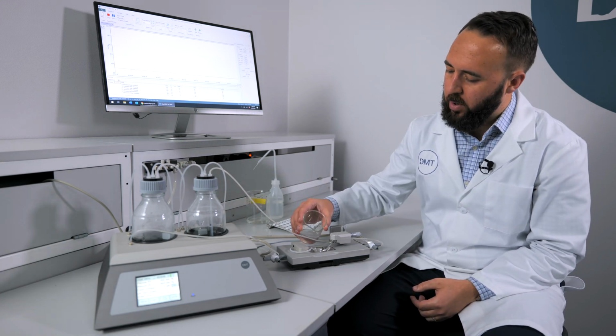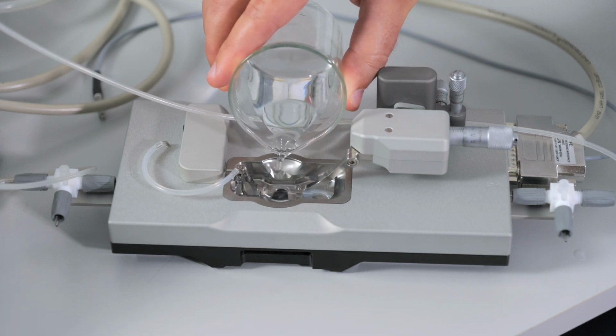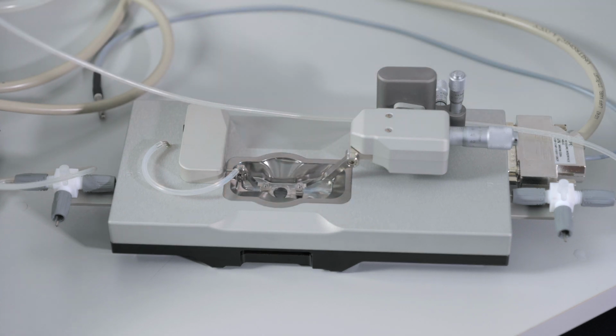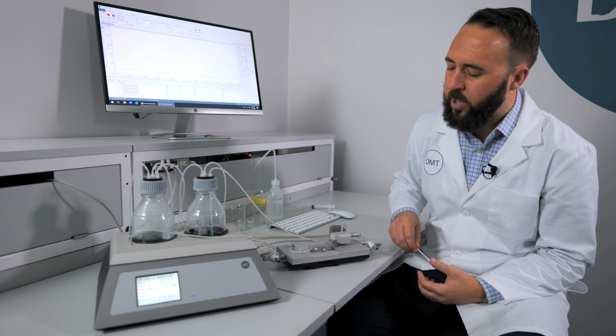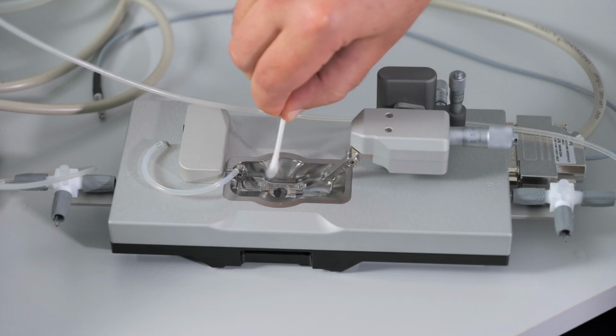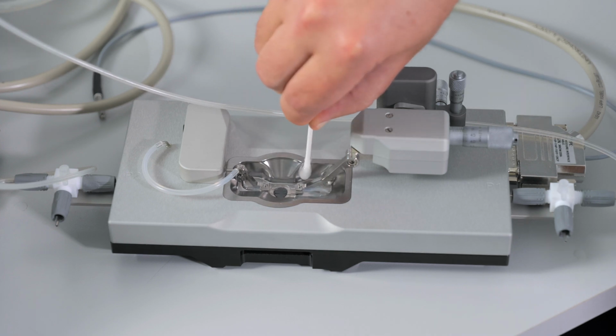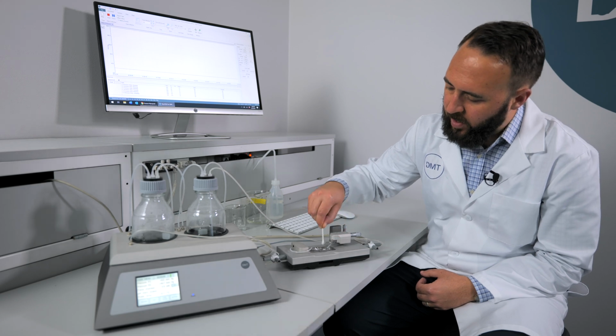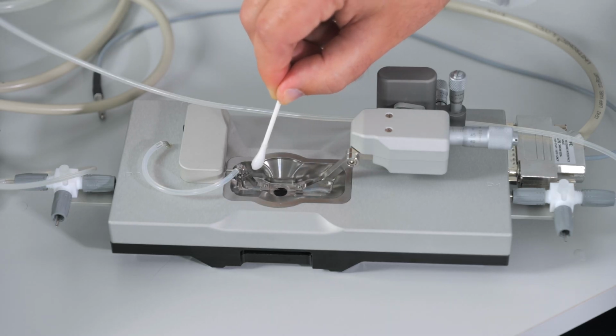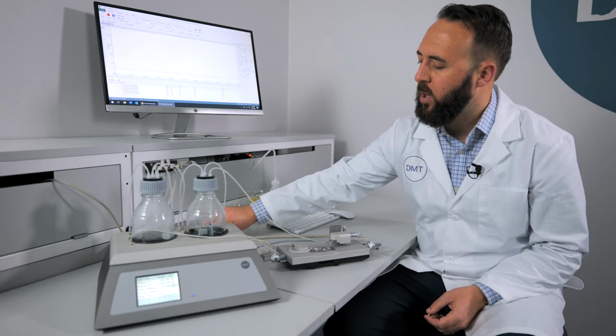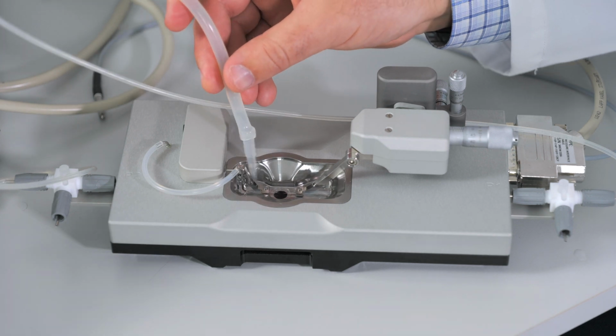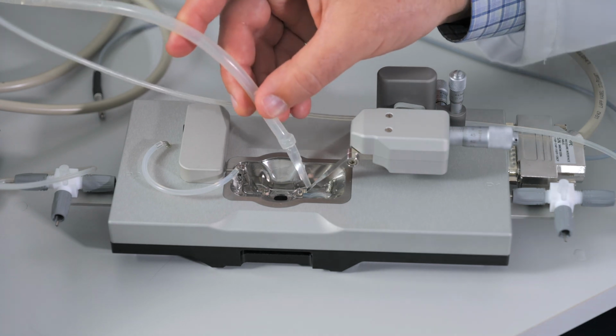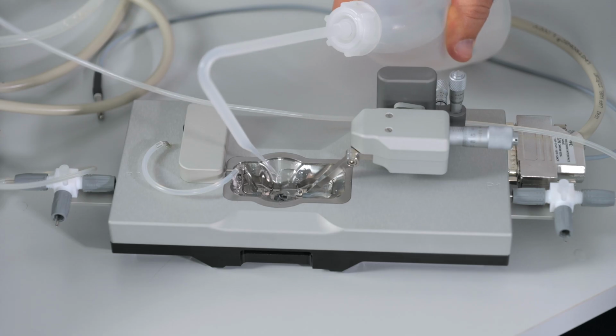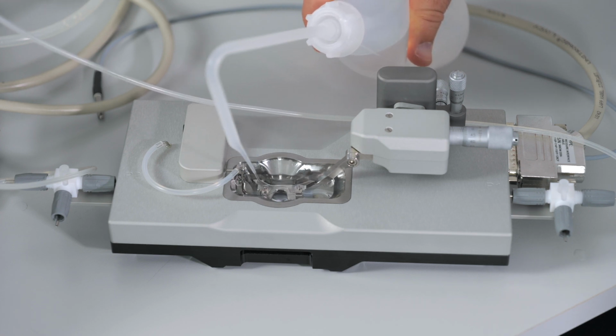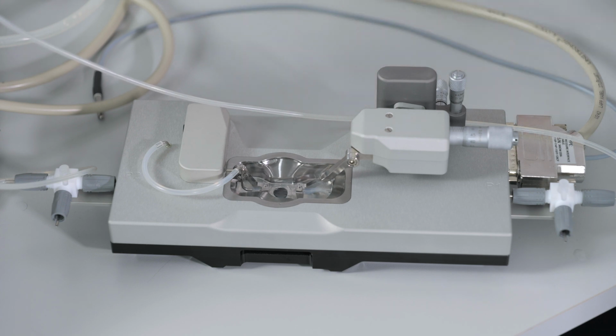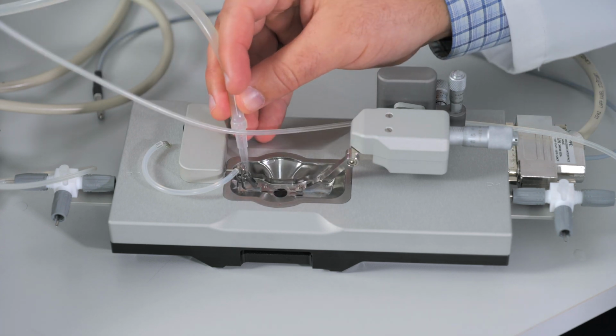You will fill the chamber with acetic acid and let it sit for 2 to 3 minutes. While it is sitting there, you can use a cotton swab to rub down the edges of the chamber. Be careful when doing this not to severely hit the force transducer side. After 2 minutes, you can remove the acetic acid and then do 3 thorough water washes of the chamber. Fill it to the top. And then empty the chamber.